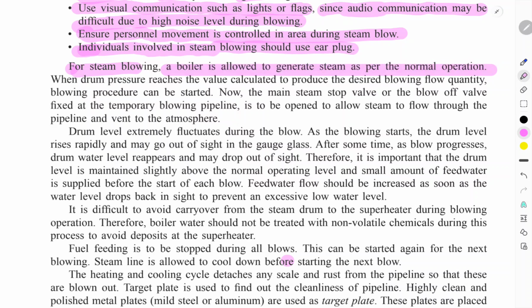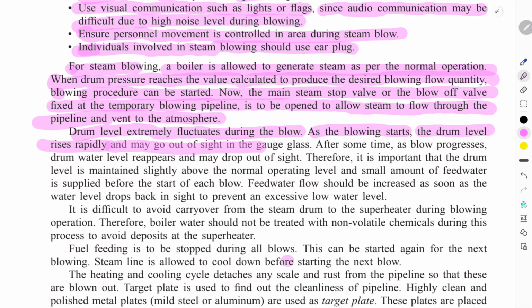For the steam blowing, the boiler is allowed to generate steam as per normal operation. Okay. When the drum pressure reaches the calculated value, the blowing procedure can be started. The main steam stop valve, blow off valve, and the fixed temporary blowing pipeline are opened, allowing the steam to flow through the pipeline and vent to the atmosphere. The drum level fluctuates extremely during the blowing. When blowing starts, the drum level rises rapidly and may go out of sight in the gauge glass.